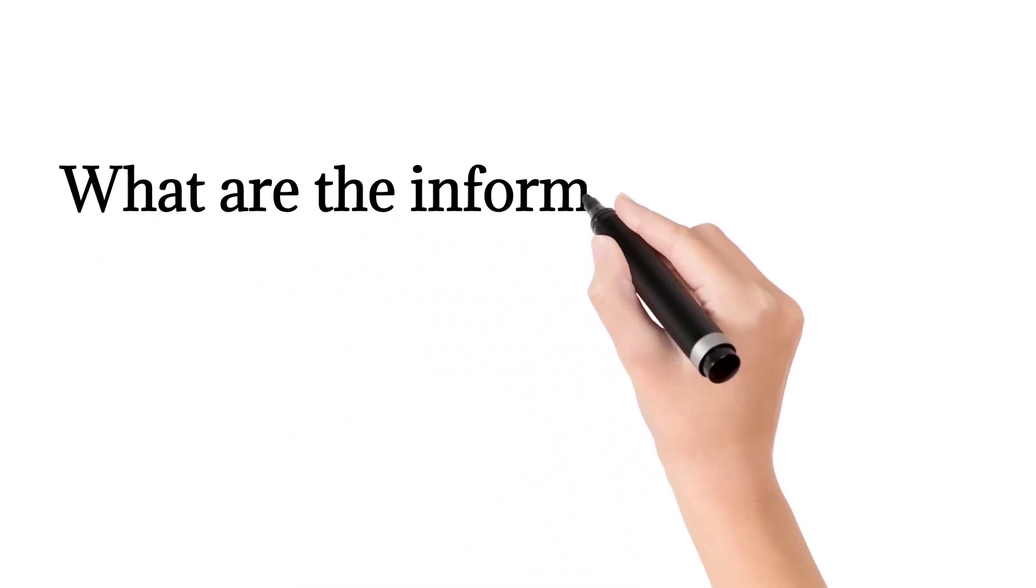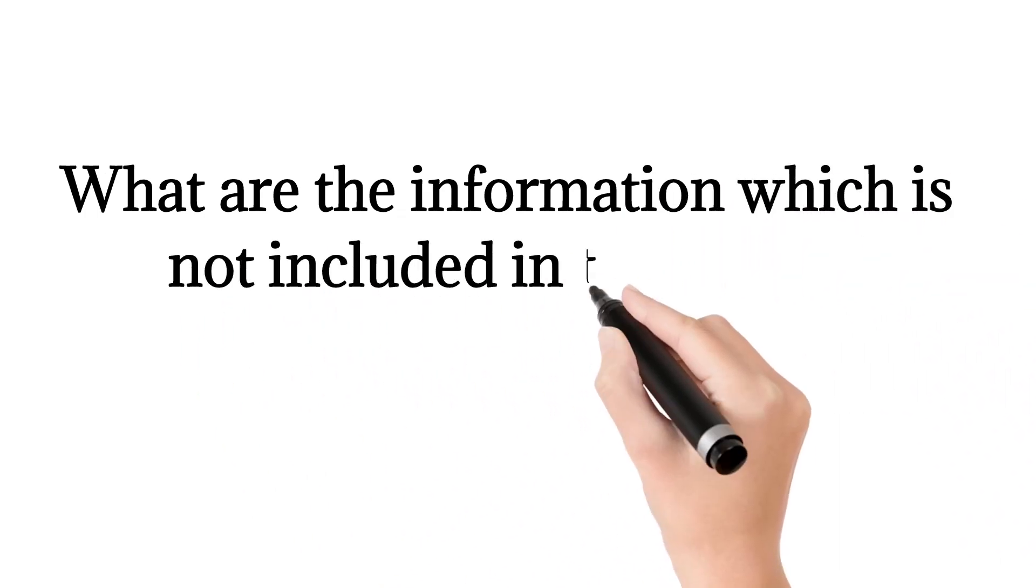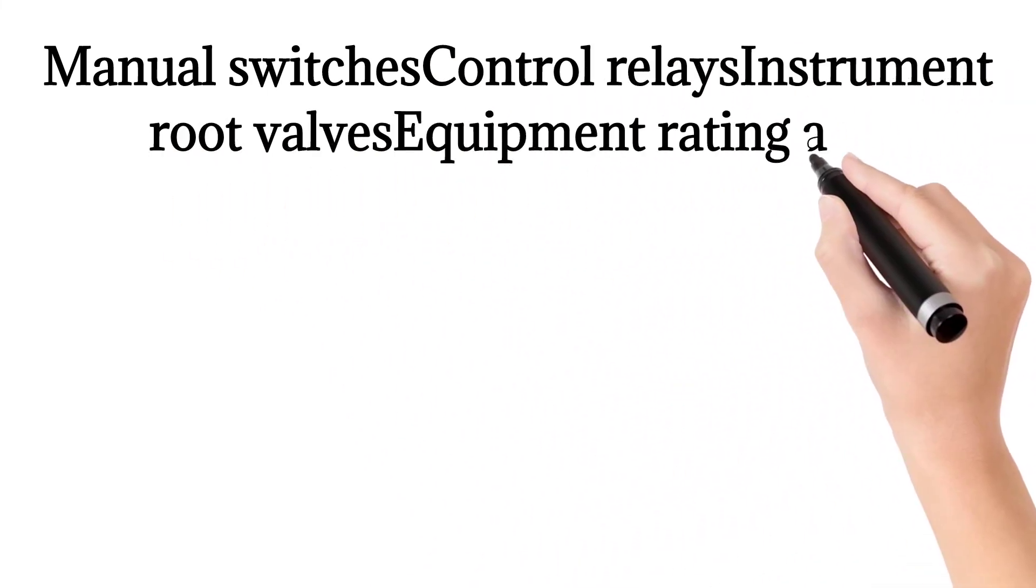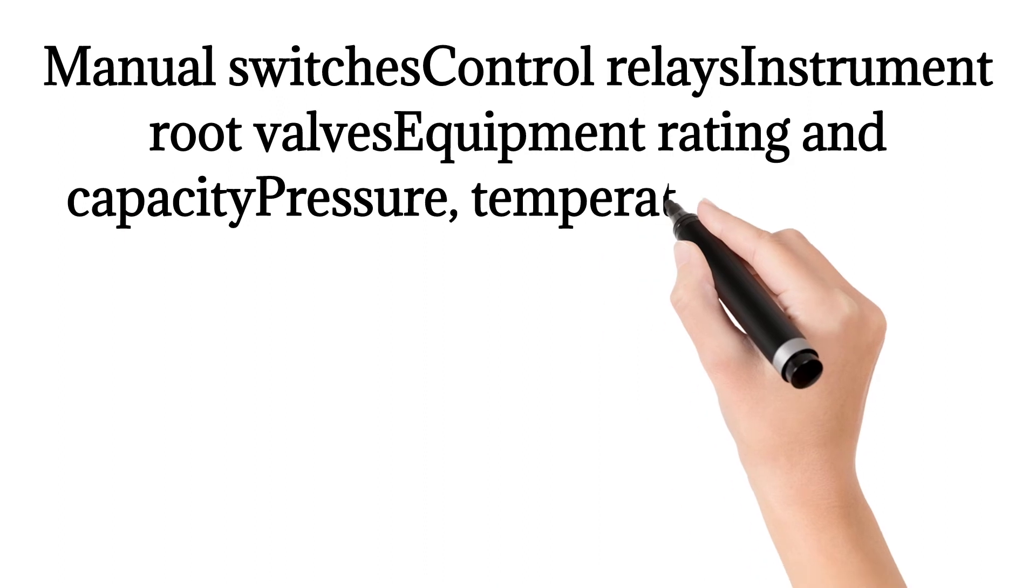What are the information which is not included in the P&ID? Manual switches, control relays, instrument root valves, equipment rating and capacity, pressure, temperature, and flow data.